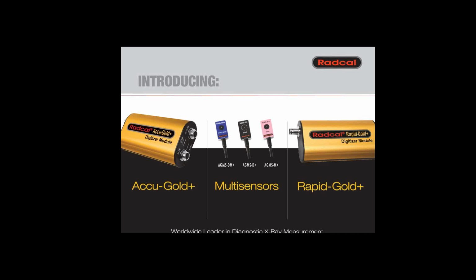The Rapid-Gold+ is a scaled-down version of the Accu-Gold+, utilizing the same Accu-Gold software, but only utilizing multi-sensors in the invasive MA device or non-invasive MA clamp. It does not accept any ion chambers, and it can be used for measurements requiring the use of solid-state multi-sensors only. This is designed for the service professional or biomedical engineer to obtain all parameter measurements with ease.